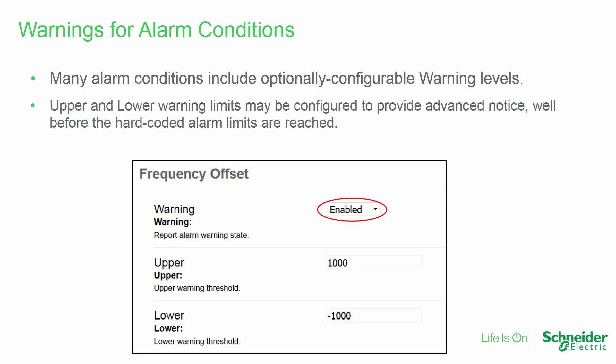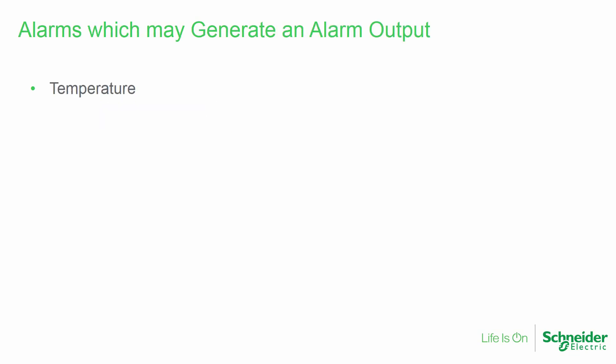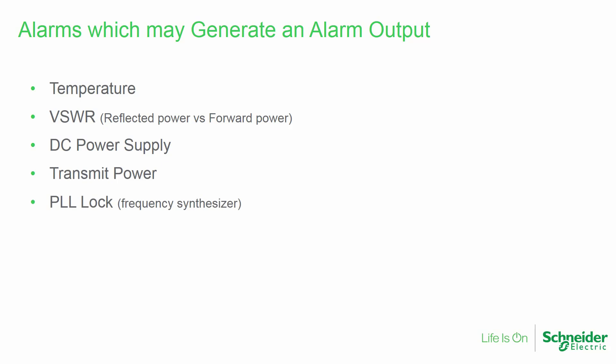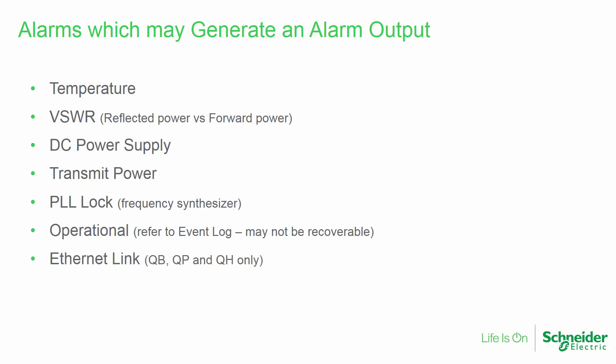Many alarm conditions in the QData radio include optionally configurable warning levels. These upper and lower warning limits may be configured to provide advanced notice well before the hard-coded alarm limits are reached. Numerous conditions are monitored which may generate an alarm output or a warning. These include temperature, VSWR (a comparison of reflected versus forward power), DC power supply voltage, the measured transmit power, PLL lock (which monitors the radio's frequency synthesizer), the operational alarm representing issues which may not be recoverable, ethernet link connectivity, and the cooling fans on the rack-mountable units.